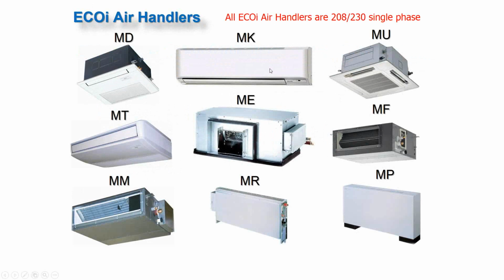This does not have a built-in pump. If you needed a condensate pump, you can get a third party for this. Next is the MU. This is a 3x3 four-way ceiling cassette. This also has a built-in lift mechanism for condensate removal. Here we have the MT, which is our ceiling suspended unit. This unit is equipped with a fresh air knockout, perfect for reintroducing fresh air to a space if that's needed. It's perfect also for classrooms or long hallways. This has a long throw. This could throw supply air up to 40 feet. That's why it is good for long hallways or corridors.